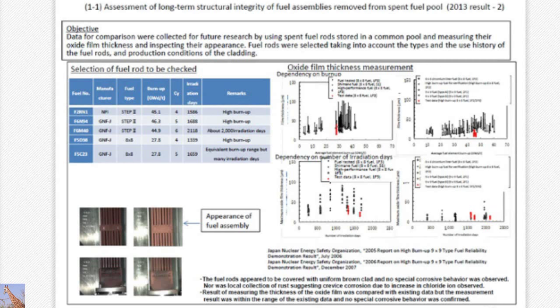Within the common pool, there has been fuel included. Looking at outside observation and the oxide film — because fuel has been kept within the pool, we wanted to see the situation inside the spent fuel. From number four, the fuel has been retrieved for analysis. There are different types of fuel, differences in type and irradiation time. This is covered by brown cladding and there was no particular corrosion found. In the past, JNES had taken various different data, and the new data taken this time — shown in red — represents the thickness of oxide film, which was kept within the scope of previous data.